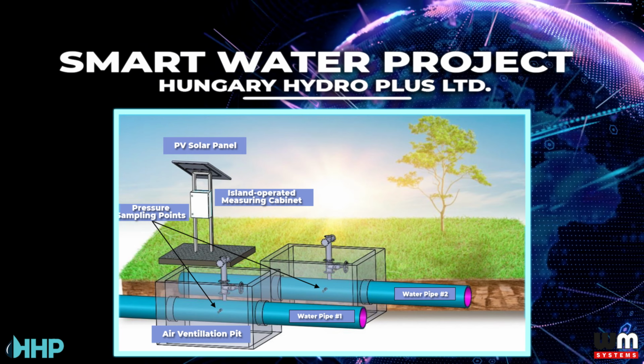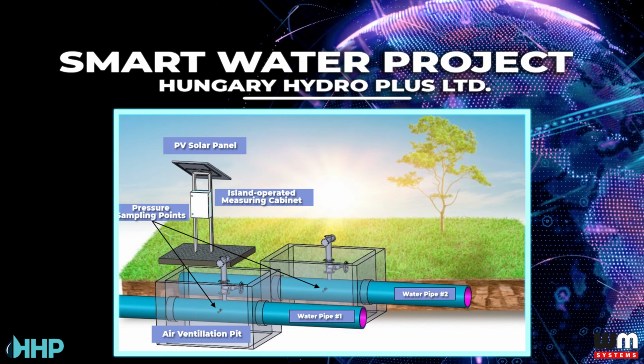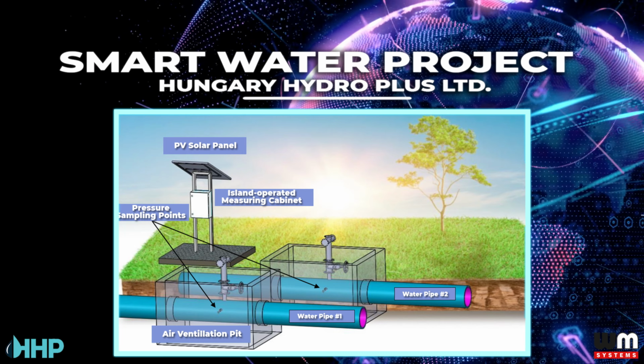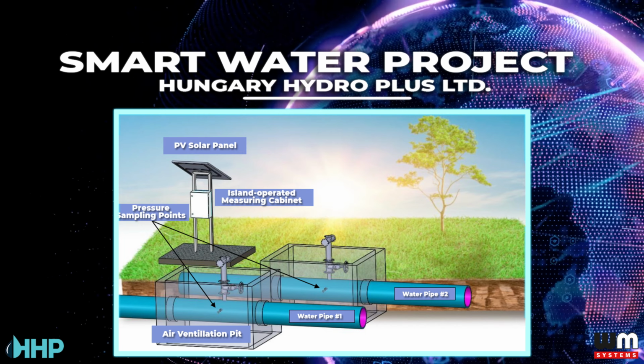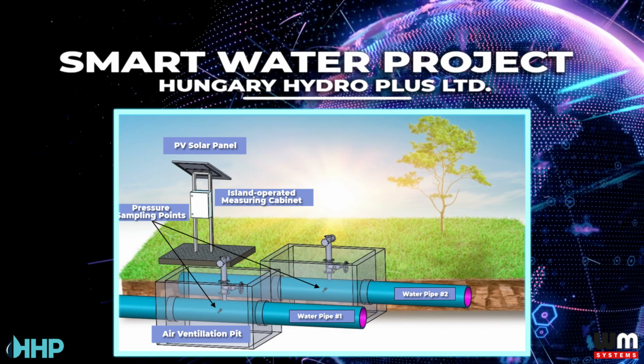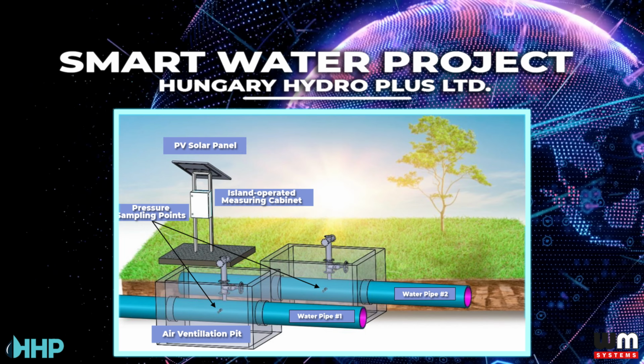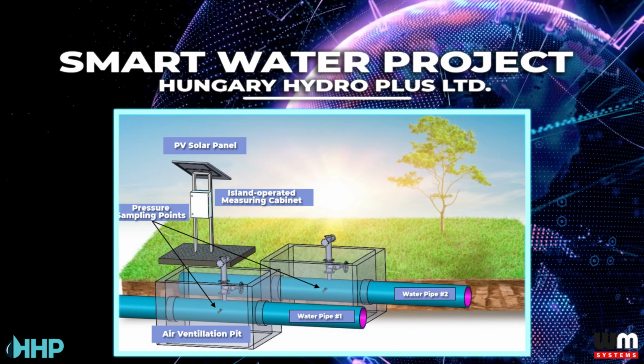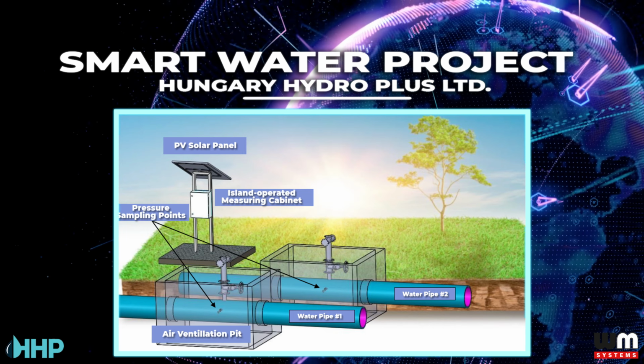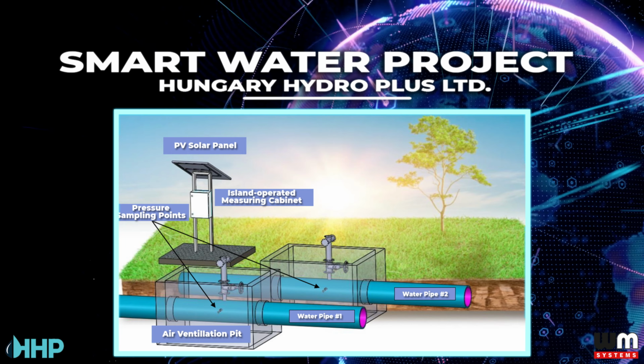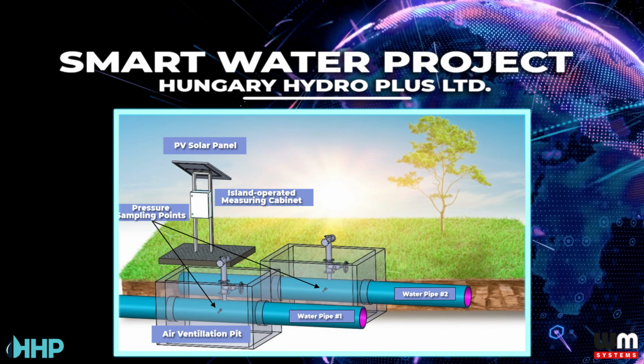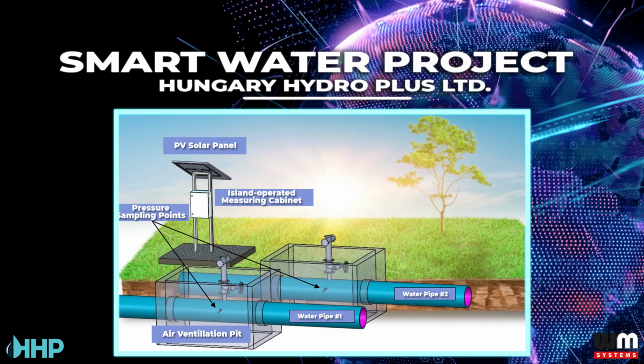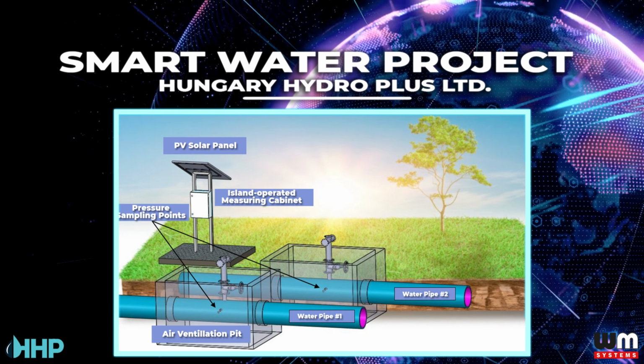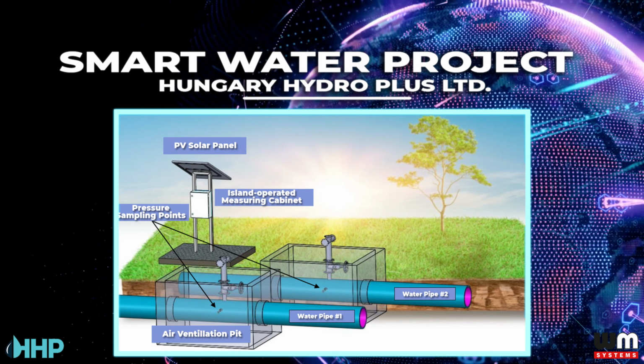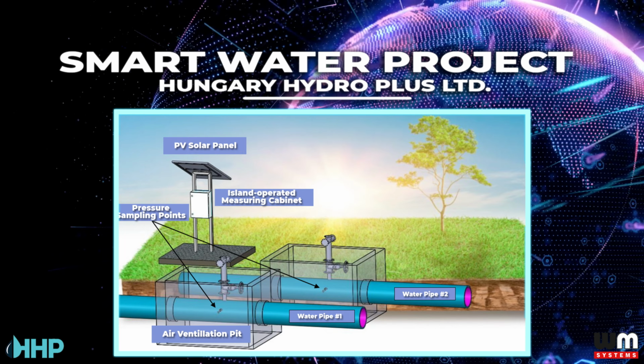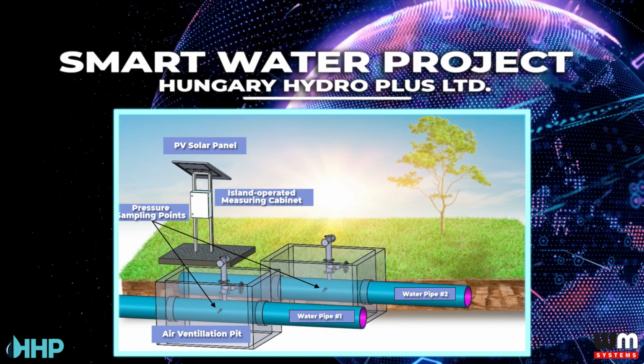The pressure measurement setup consisted of an Advantech 4 to 20 mA transmitter connected via Ethernet to the router, while the IORS 485 concentrator handled fault signal collection. Data communication was performed via Modbus TCP protocol, with transmission to the central monitoring system over the LTE network. The system was capable of issuing alerts, for example, in the event of a power fault, such as a depleted PV battery, or critically low pressure, enabling timely intervention by operators.